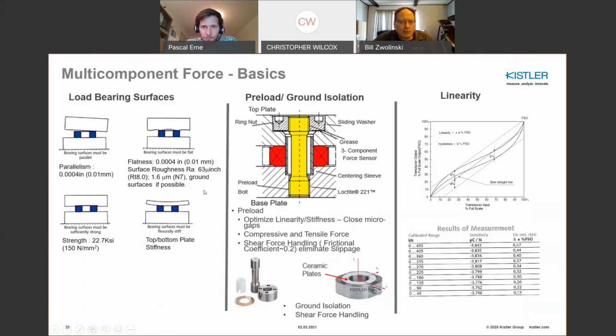Preloading is very important to getting the most out of your multi-component force solution. The preload bolt, as you see, here's the force sensor in red. You have the preload bolt going through. It has threads on the bottom and threads on the top. There's a ring nut at the top. There's actually a sliding washer right between the ring nut and the surface of the ring of the top plate, and that's greased so that you don't bind up when you're preloading the assembly. So it works quite well and is quite easy to use.